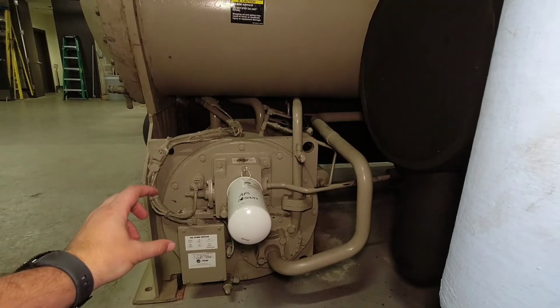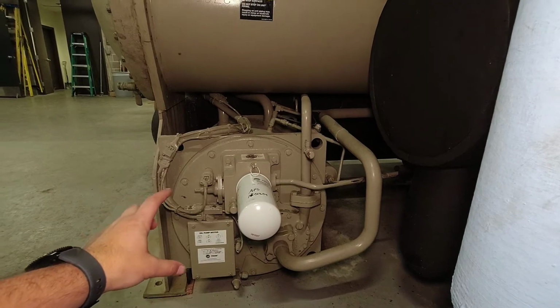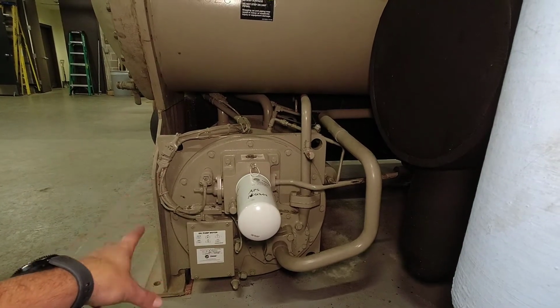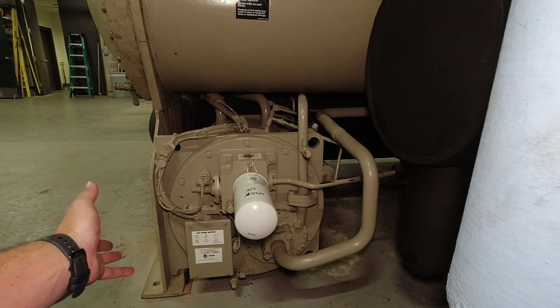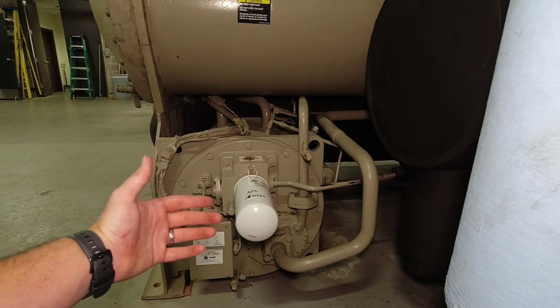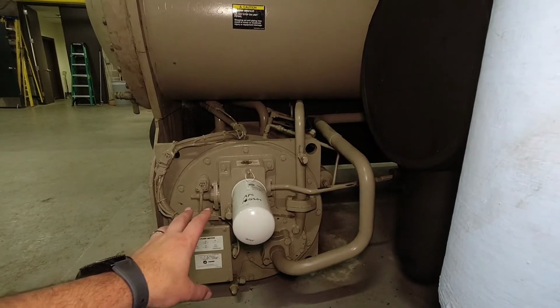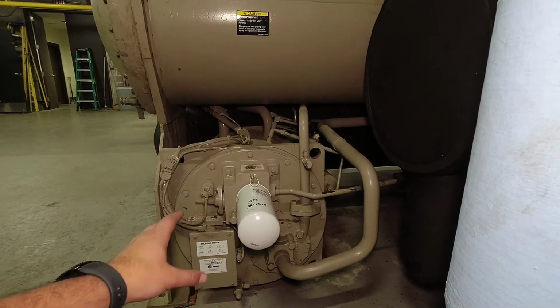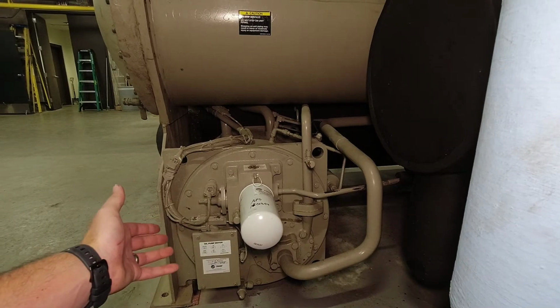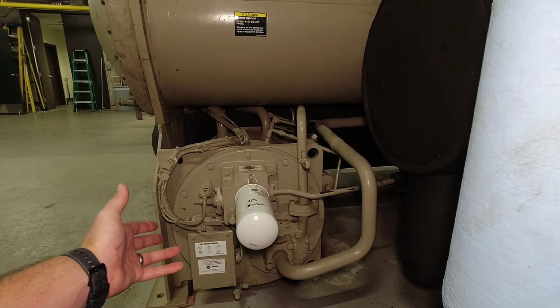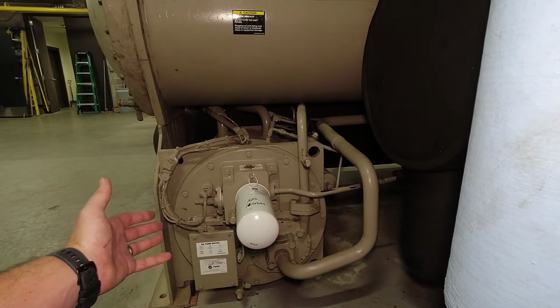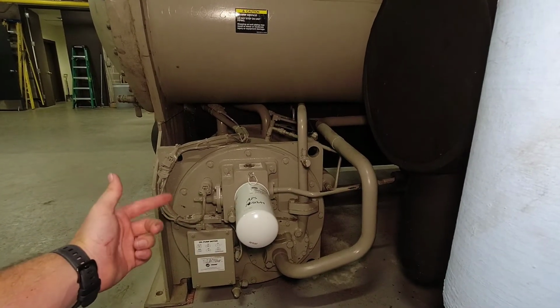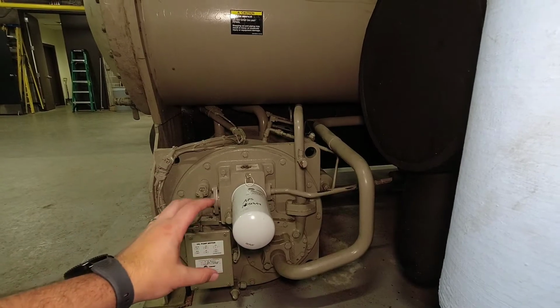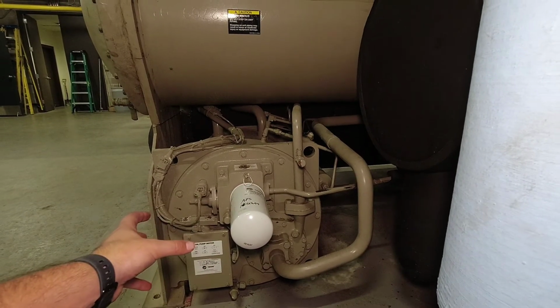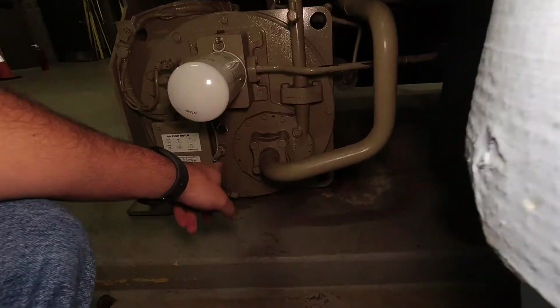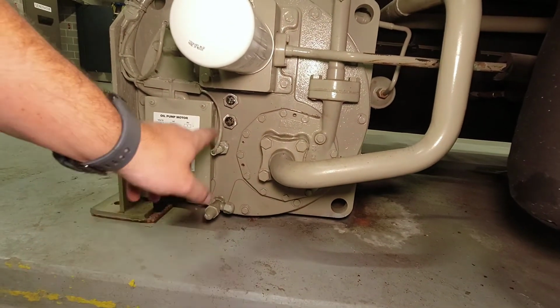And that's because we need to keep it at a very specific viscosity. Anything above or below that, we get too far outside of our viscosity range, which affects its ability to lubricate all the bearings properly. This chiller does have journal bearings, meaning that it does require heavy oil lubrication in order to protect the bearing, especially during regular operation. Those journal bearings require oil to help make part of that seal on the journal. You have your oil temperature sensor, and you have your oil sight glasses.